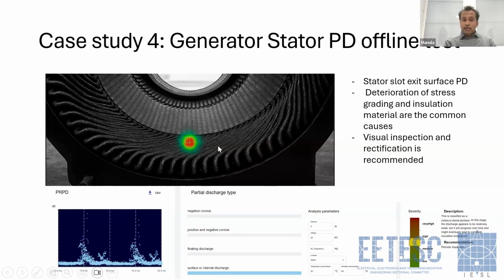In this case, the camera is locating a partial discharge around the area of the slot exit, and the PRPD pattern suggests it as a surface discharge. Usually this kind of discharge happens because of damage or deterioration of the winding insulation. Particularly in this area we have the stress grading material insulation, so that might get damaged as well. So it is often recommended to do a visual inspection if you detect this kind of thing during an offline test, so that we can see whether there are damages or white powders accumulated on this insulation, and we can repair the damages if we find any.